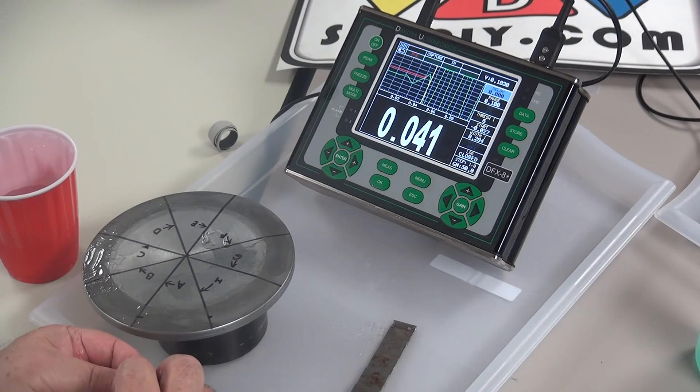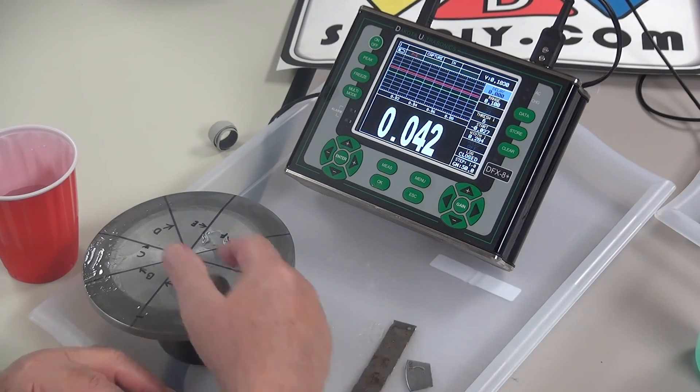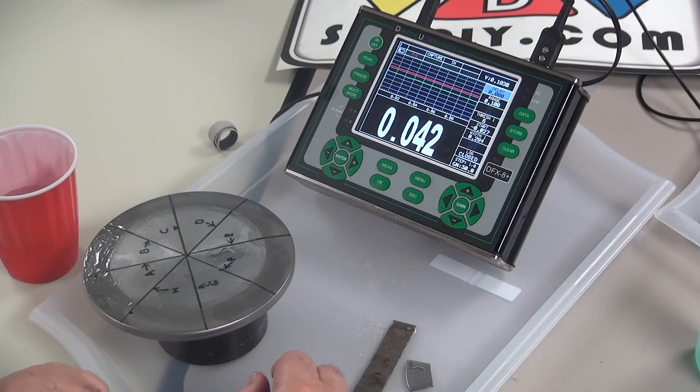The phase of the signal actually reverses over the moly. So we have to change the gate setting from negative to positive when we go to the actual sample. Sectioning the sample, creating some actual knowns to calibrate to will improve the situation.